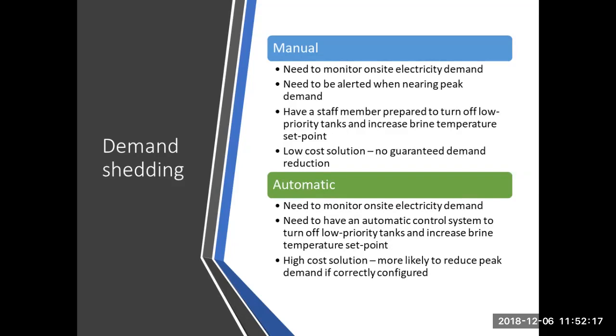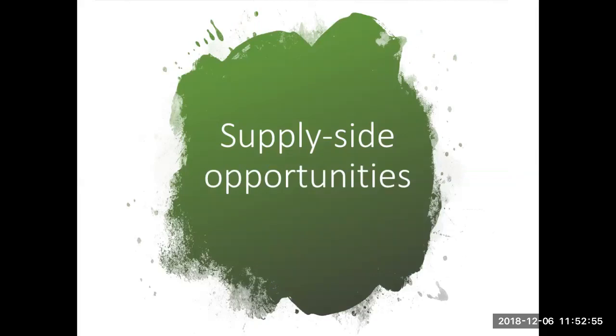But if you set up an automatic system on your tank farm, it can be connected to your monitor, so you're monitoring your demand, and when you're, say, within 10 or 20% of hitting that peak demand and incurring more charges, you can automatically turn off low priority tanks and increase the brine temperature set point to cut back and basically save that money. Setting it up automatically is obviously a higher cost solution, but you're more likely to reduce your peak demand if you've got it correctly configured. So that's your demand side opportunities.